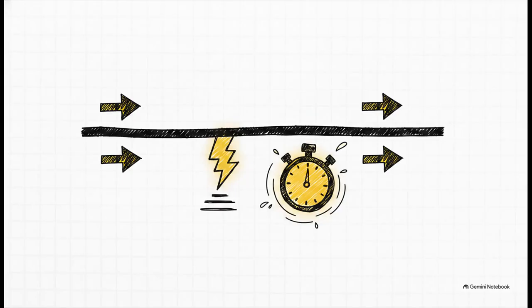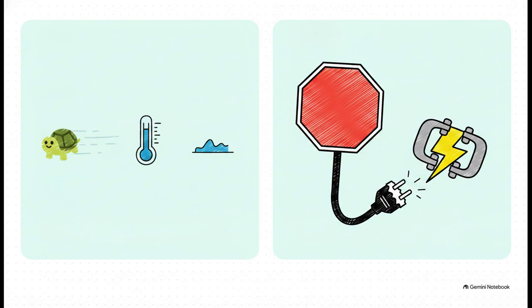And because speed is literally everything in this scenario, we have KCL, or Kirchhoff's current law, leakage current monitoring. By constantly calculating the residual of the 3-phase currents, basically double-checking if what goes into the motor exactly equals what comes out, this algorithm can detect a tiny milliamp level leak to the ground and react in just 2 milliseconds. On top of that, there's a completely separate background software process looking for high-frequency electrical resonances. It's basically a canary in the coal mine, warning of degradation long before it reaches a critical level. All of this builds a brilliant 2-tiered safety fallback strategy. If the system senses light degradation, the motor enters a safe limp home mode.